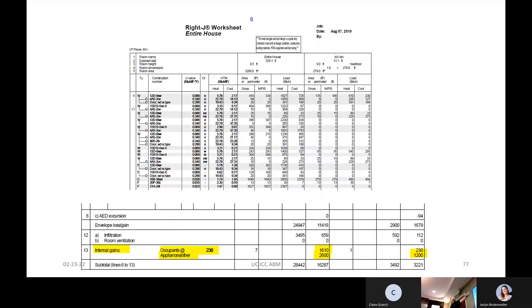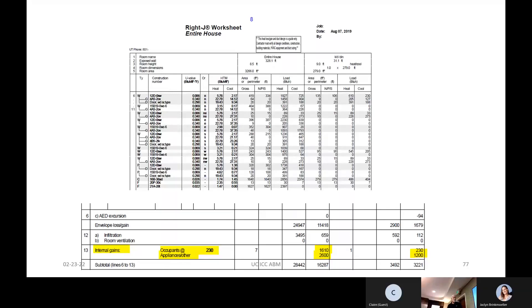At first glance this looks really confusing with all these numbers, but it describes — there's a W for wall, glass, and a door. These numbers coincide with numbers in Manual J that describe the assembly. This column is the U-factor. Rather than just construction components, you can go to this column and verify U-factors. Remember we talked about HTM? It's U times delta T — there are those numbers. Notice it says gross area, then net, heating load, cooling load — that's for the whole house. It totals up down here just like the short form. There's tons of information on that page.